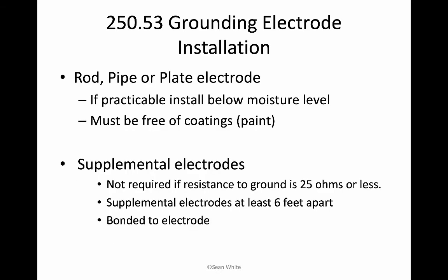Then this NEC thing tells us how to install stuff. The nerve of them. But if you're going to install a rod, ground rod, a pipe, or a plate electrode, you want to install it, if practicable, below the moisture level. And it must be free of coatings like paint, of course, because that's not going to be very conductive. Paint is not very conductive. Supplemental electrodes are not required if resistance to ground is 25 ohms or less. Sometimes you can even measure the resistance to ground. Supplemental electrodes must be at least 6 feet apart. There's some AHJs, authorities having jurisdiction, where they require supplemental electrodes. That might have to do with how conductive your earth is.